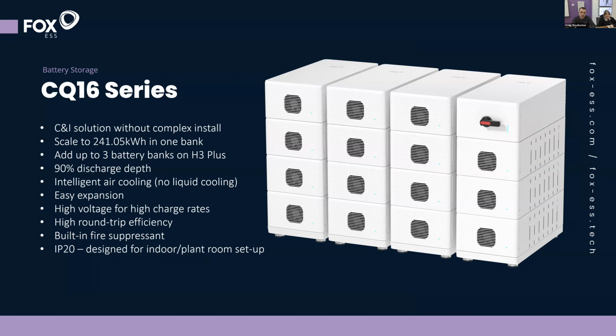They serve their purpose—there are certain applications where that kind of solution works. The issue with them is that maintenance costs are quite high, because you have things like liquid coolants and refrigerant gases in there, which have to be serviced and maintained annually or biannually, adding to ongoing cost. So what we've done here is produce a C&I solution that's very scalable and takes away a lot of that maintenance—it's much more modular, but enables you to scale really high.